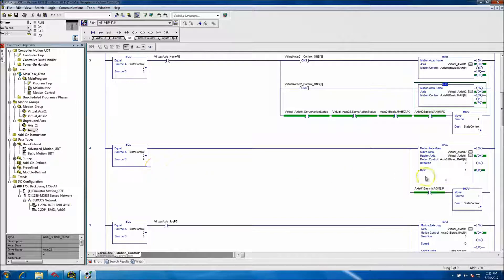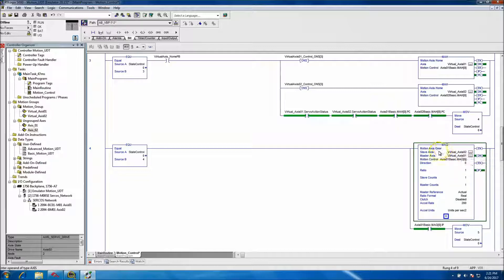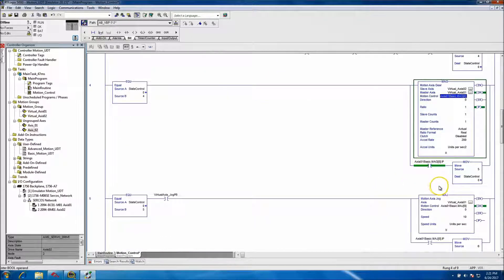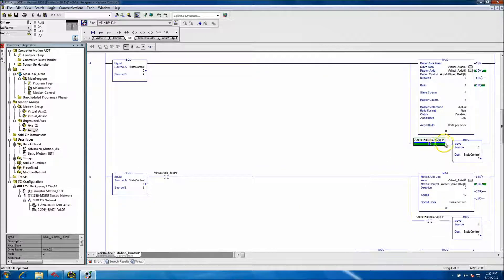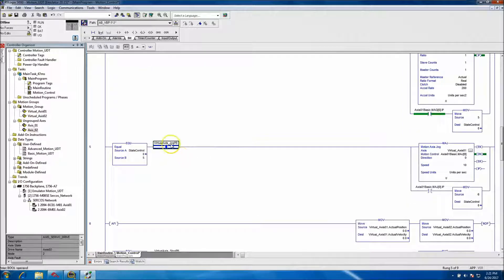As soon as state 3 is complete it goes to state 4, which links Virtual Axis 1 to Virtual Axis 2 using a Motion Axis Gear (MAG) command. We're again using the UDT we created. As soon as the IP (In Process) bit is on, we know both axes are geared together.